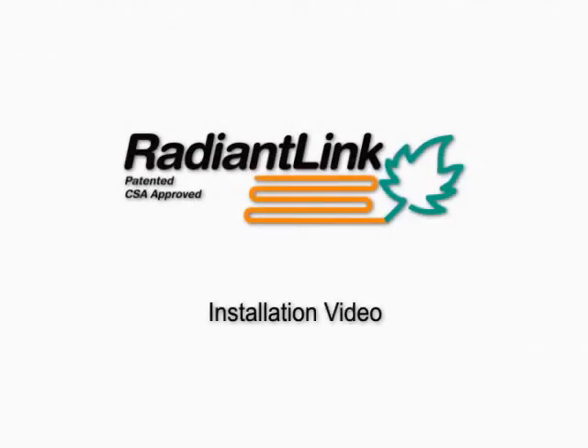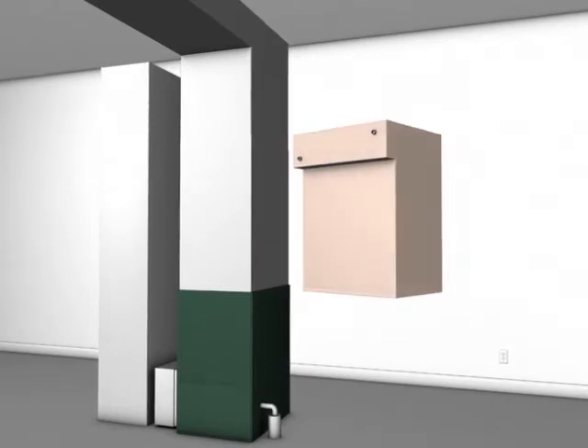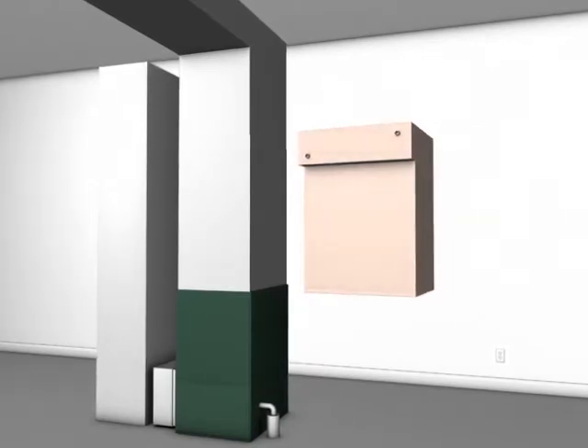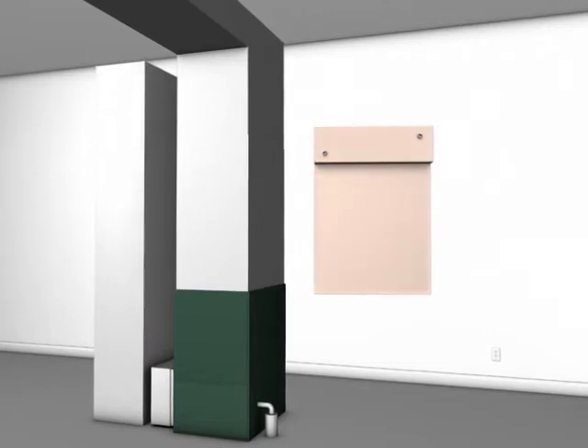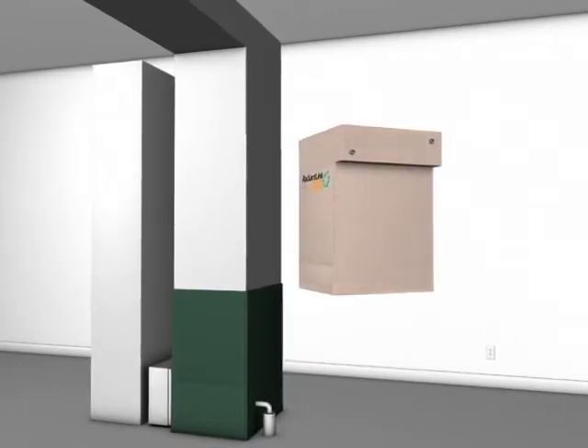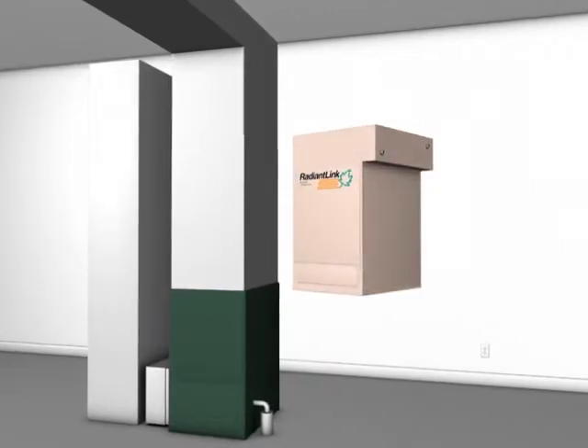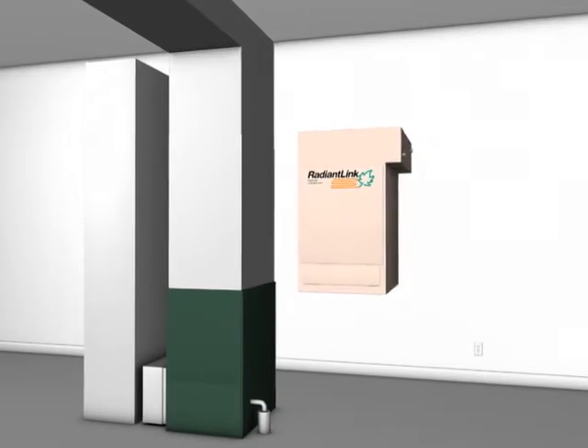Locate and read the complete Radiant Link installation instruction package inside the control panel. Determine the best orientation for the plenum. One of the large removable plenum access panels should be directly above the front of the furnace, with the plenum coil connections on the opposite side of the furnace return air ductwork.